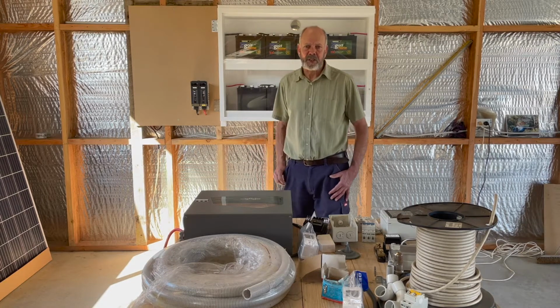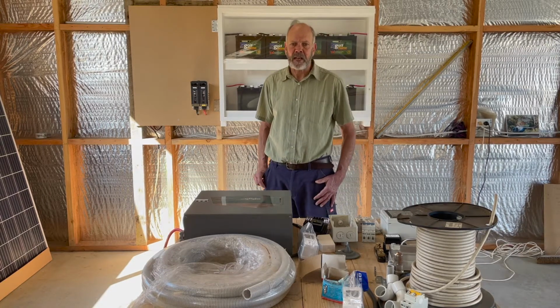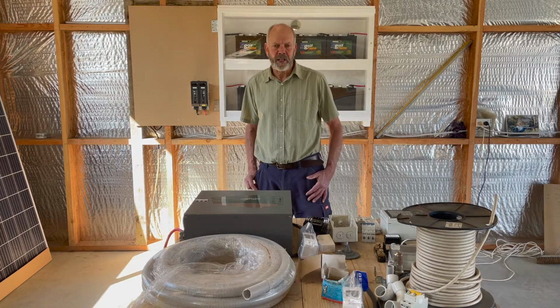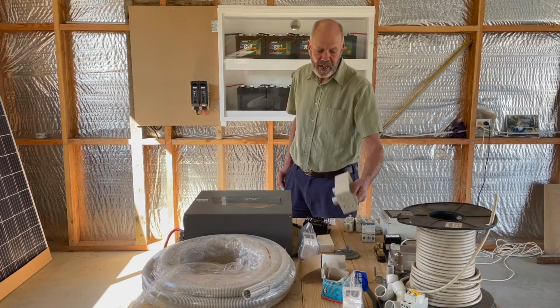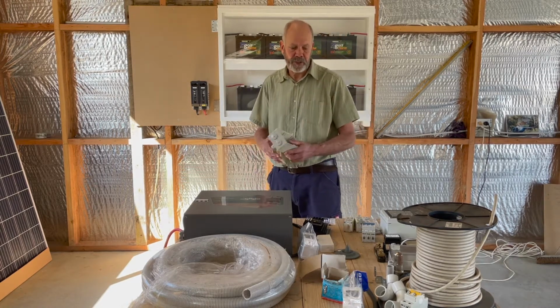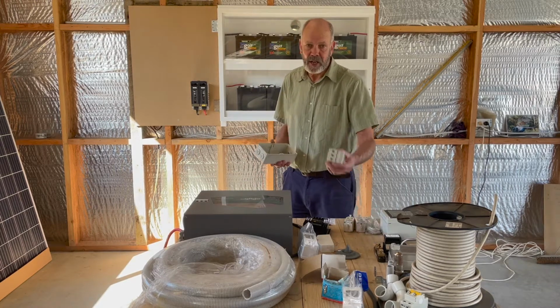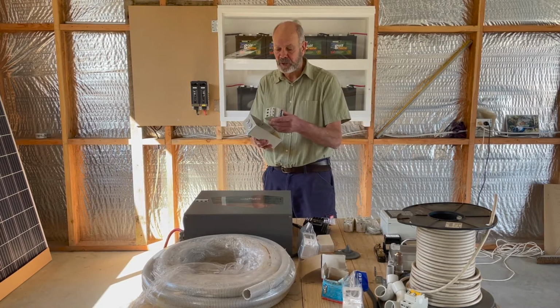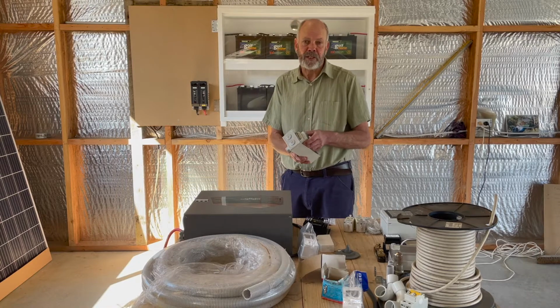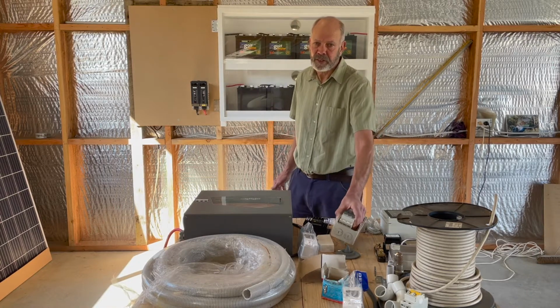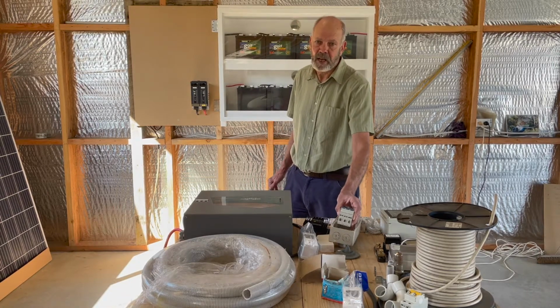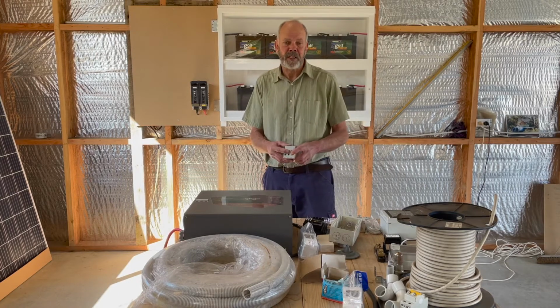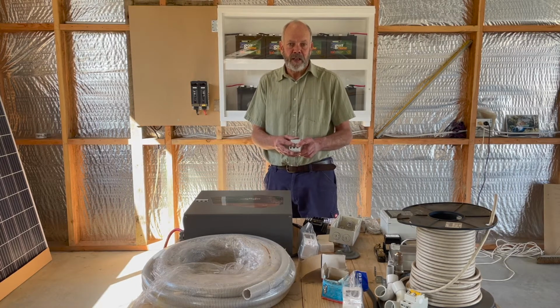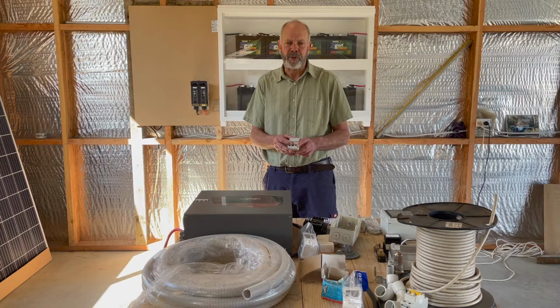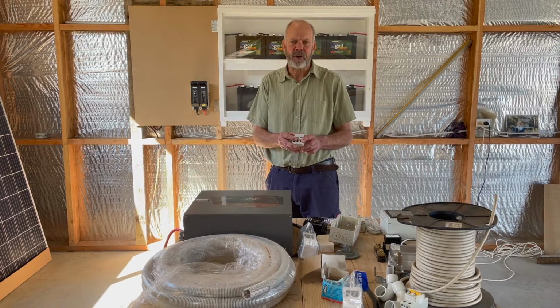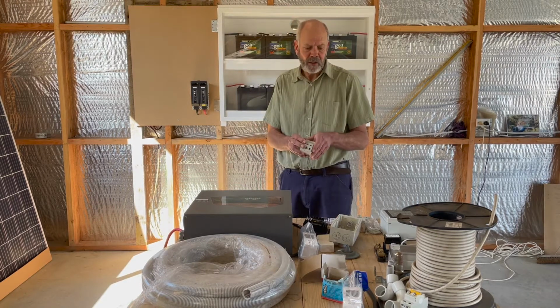To commence the installation I need a thing called a solar array disconnect, and for that I'm going to take up an outdoor enclosure. It's an electrical enclosure and that's going to house a triple module solar circuit breaker which will provide a means of disconnecting the solar array while I'm working on the system and if there's ever any fault in it. I'm going to put this disconnect on the roof. It's actually a requirement to be able to disconnect your solar array up at the solar array.